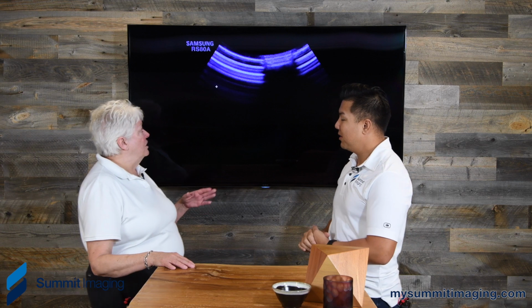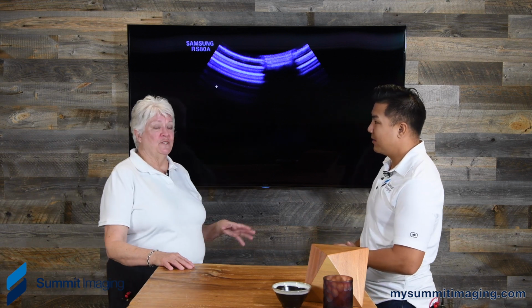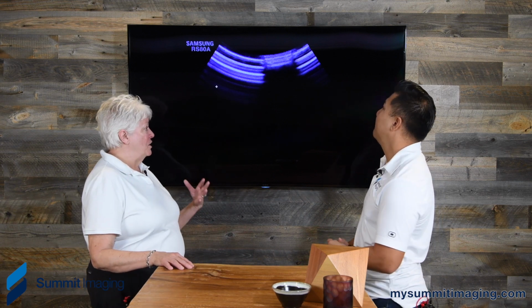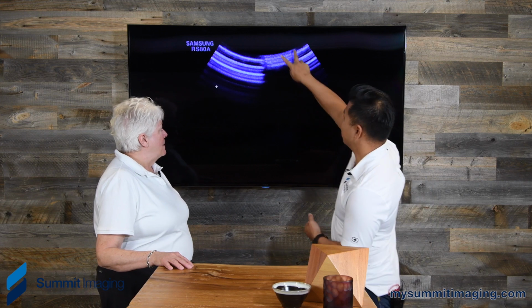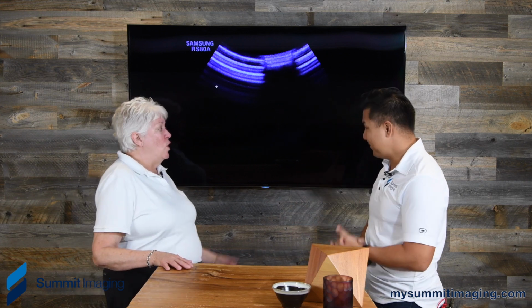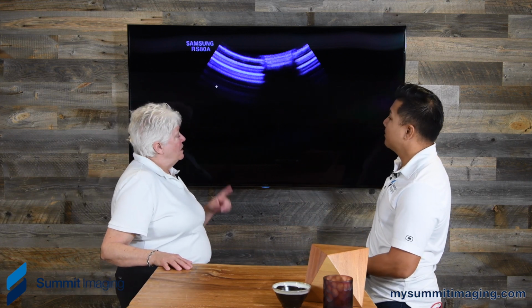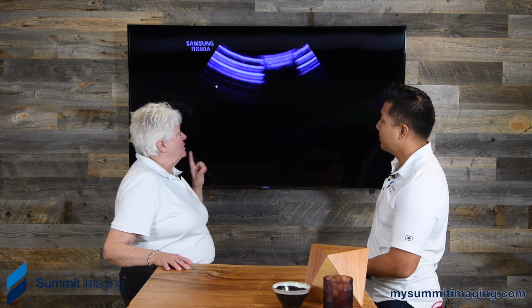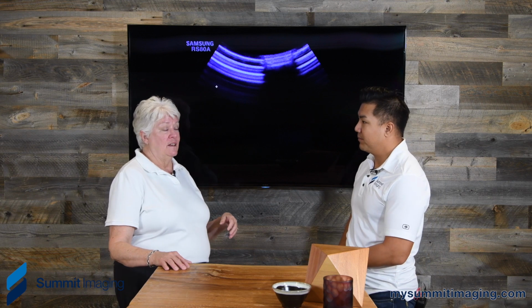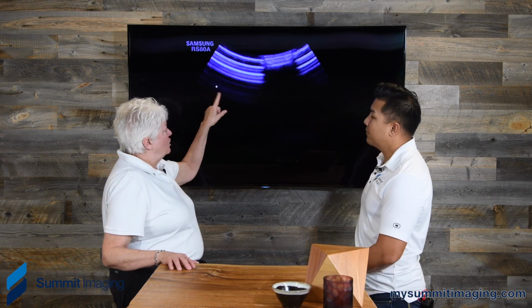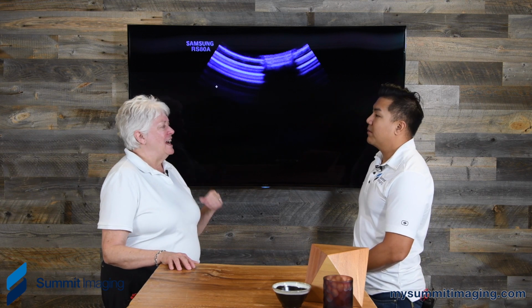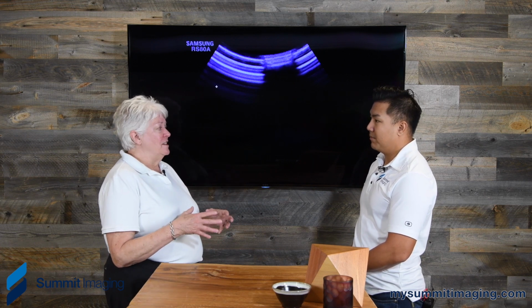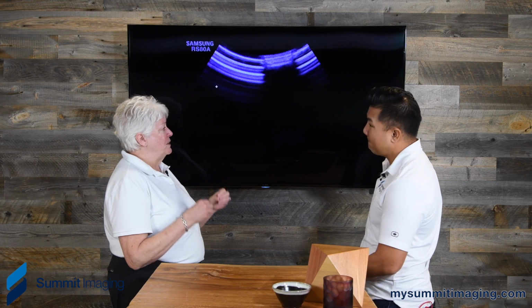Well, as a sonographer, I don't always think of the transducer as the problem. Sometimes I think of the software in the system. Maybe there's a little bit of gel right there, or I need to move. Yeah, or there's a software issue. But one of the things I do know has happened, and this is with older transducers, I don't know if this is still happening today, but I worked in Colorado, so I worked at altitude.